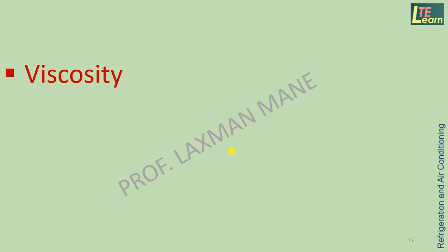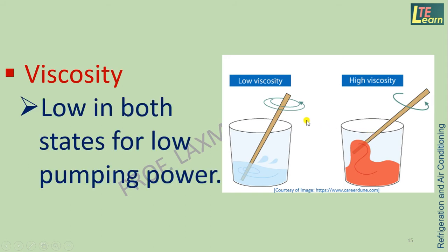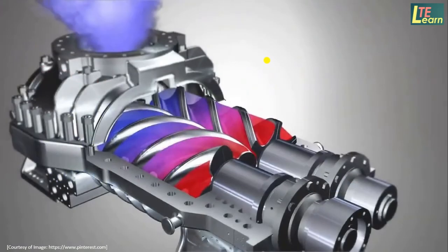Viscosity is the resistance offered by a refrigerant fluid to its flow. When refrigerant has low viscosity, it is easy to move or handle, but when more viscous it is difficult to move and takes more effort. In both states — liquid and vapor — viscosity of refrigerant should be low in order to reduce compression power taken by the compressor.